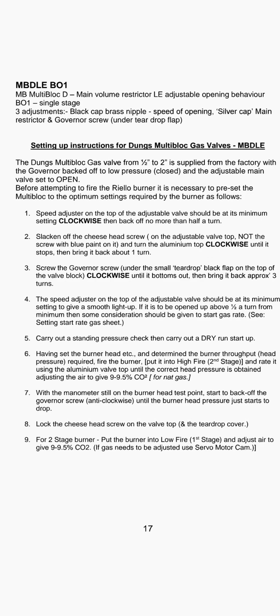Step nine for a two-stage burner: put the burner into low fire first stage and adjust the air to give 9.5% CO2. If the gas needs to be adjusted, use the servo motor cam.